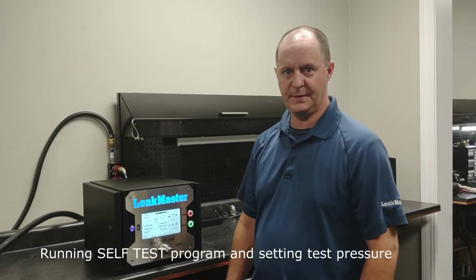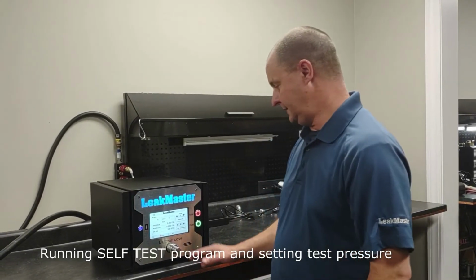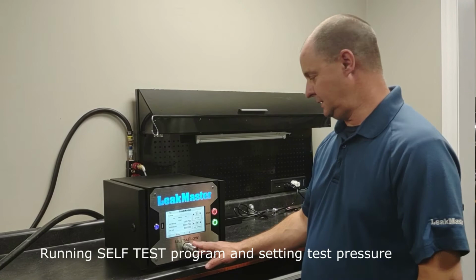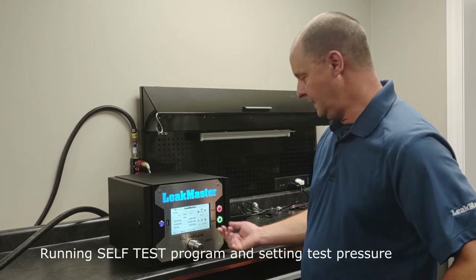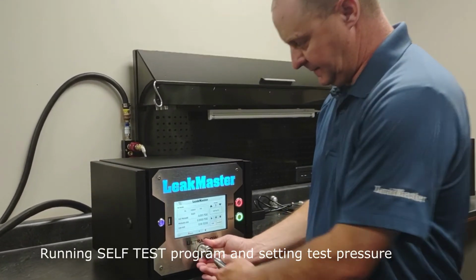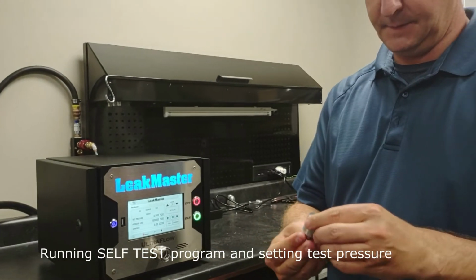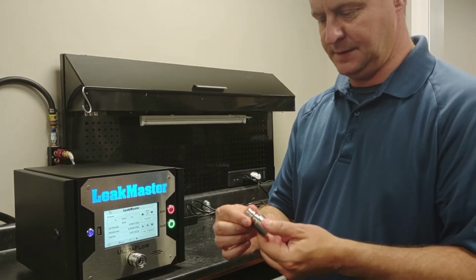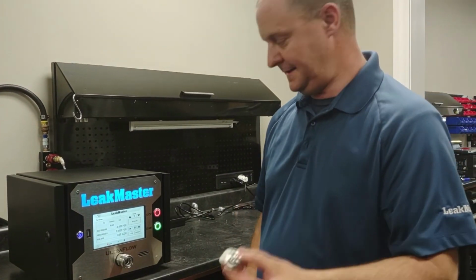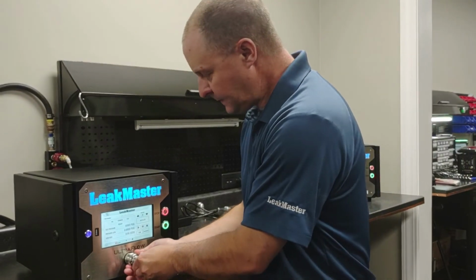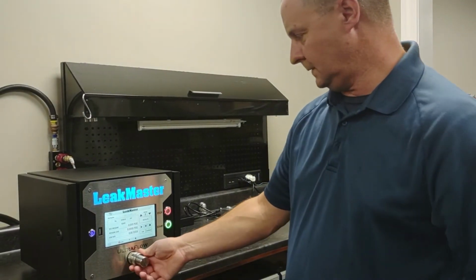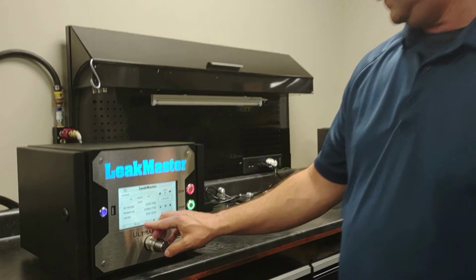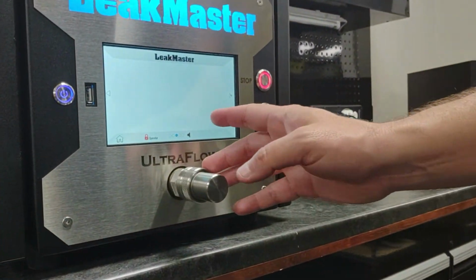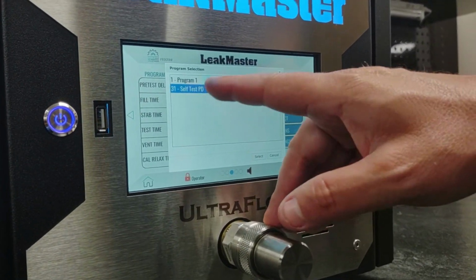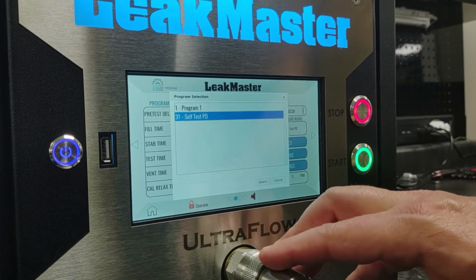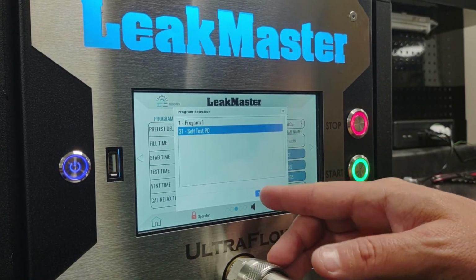Now that we've booted up the unit, the first thing we're going to do is do a self-test on the unit to ensure that the internal manifold is leak-free. When this unit is shipped to you, it's going to be shipped with a plug in it. This is essentially just like the Swagelok QC8 fitting, except it's a deadhead. So I'm going to make sure that guy is installed, and we're going to go to our program screen, and we're going to select SelfTest PD, which is a default program on program 31.